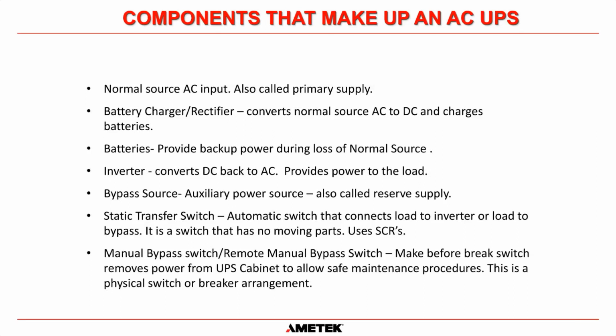Then inside the UPS, well, usually external to the UPS but part of the UPS, there will be batteries. That's the heart of the UPS. If you don't have batteries, then you don't have a backup power supply. So the batteries provide backup power during a loss of grid power. Then that DC needs to be converted back to AC because it's AC loads. The critical loads that we supply are AC loads. So the inverter converts that DC back to AC.